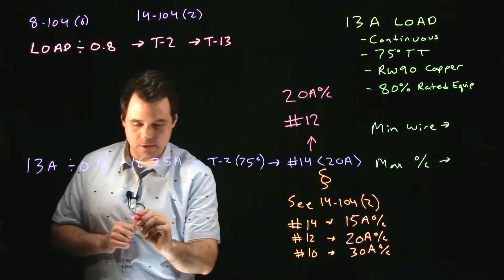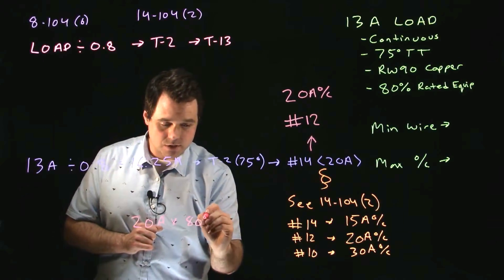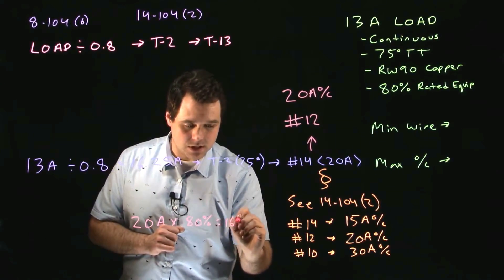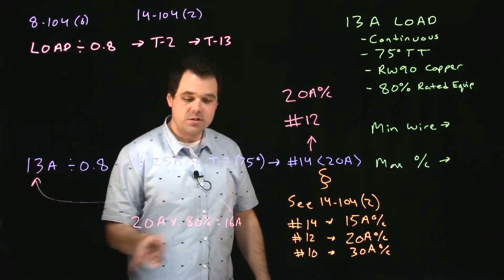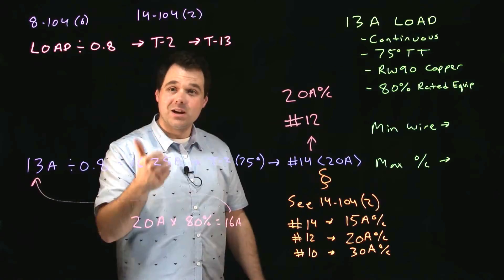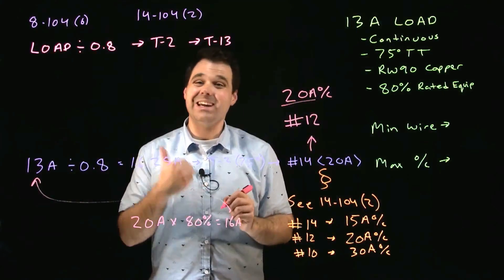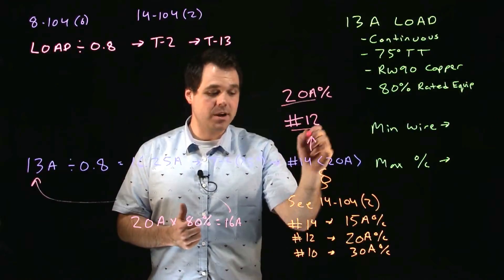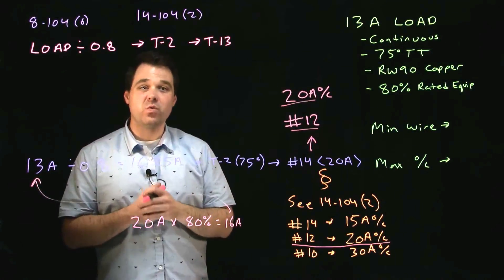If I double check, I go 20 amps times 80% or 0.8 gives me 16 amps. I compare that to my load. My load does not exceed 80% the rating of my breaker. I am good to go. Also my 20 amp OC is adequately protecting my number 12 based on that rule 14-104 sub rule 2.